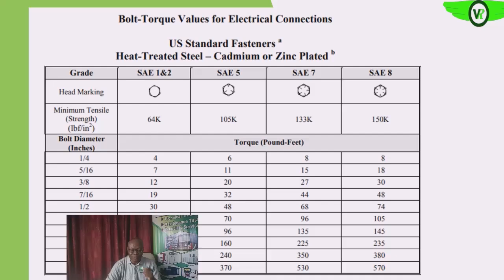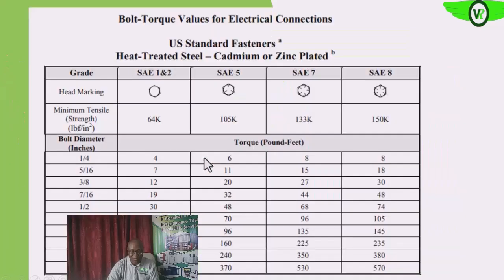So if our facility does not have any specified torque level, or the manufacturer of the equipment does not have any specified torque level, then we can use this table. If you look at it, you see that different grades of bolts have different torque levels, even for the same sizes. For example, if this nut is a half-inch nut, and maybe the grade is SAE 5, the amount of torque that will be applied is 48 pound-feet. So we'll use our calibrated torque wrench, as you can see on the screen, to do our torquing.